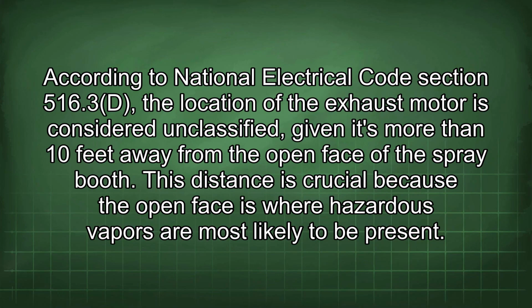According to National Electrical Code Section 516.3(d), the location of the exhaust motor is considered unclassified, given it's more than 10 feet away from the open face of the spray booth. This distance is crucial because the open face is where hazardous vapors are most likely to be present.